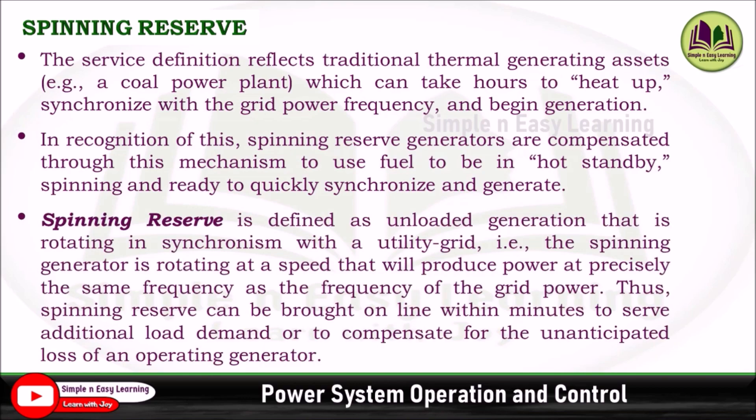Spinning reserve is defined as unloaded generation that is rotating in synchronism with a utility grid — that is, the spinning generator is rotating at a speed that will produce power at precisely the same frequency as the grid. Thus, the spinning reserve can be brought online within a minute to serve additional load demand or to compensate for unanticipated loss of an operating generator.